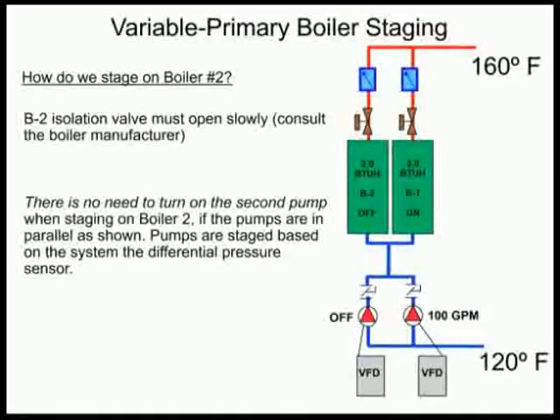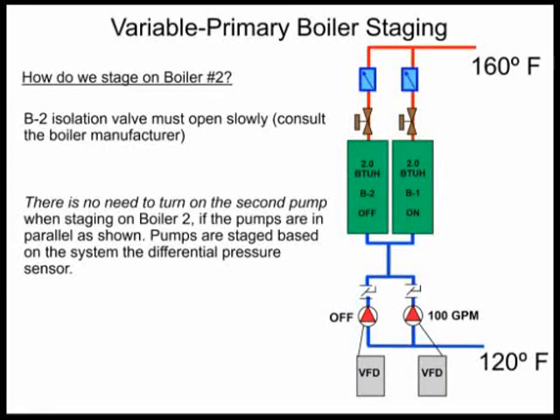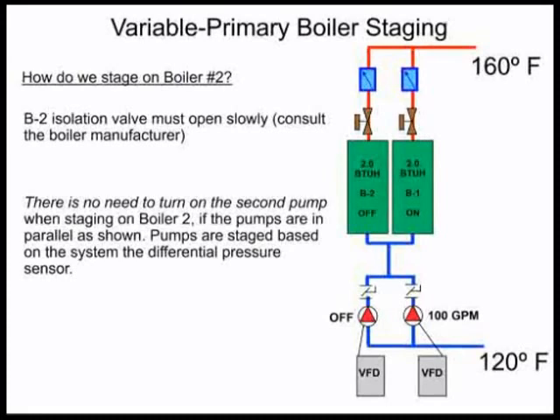Remember, there's no need to turn on that second pump when staging boiler number two. If the pumps are in parallel, one pump can run across both boilers. Keep in mind the pumps aren't staged by the boilers — they're staged on the differential pressure sensor out in the system, either by the built-in VFD controls or by the BMS. Pump staging in variable primary is not based on what the boiler is doing; it's based on what's happening in the system as determined by flow. Those two are independent of each other.